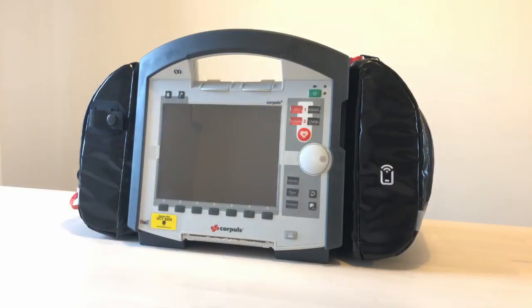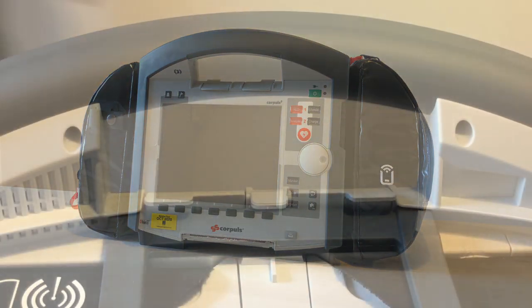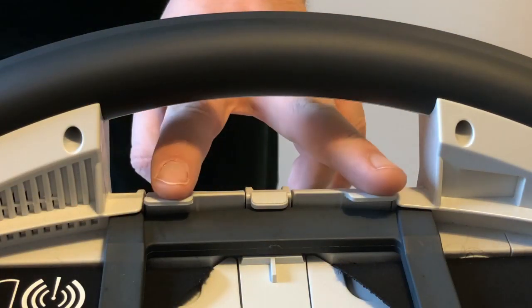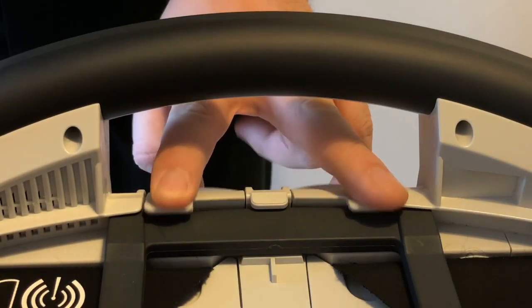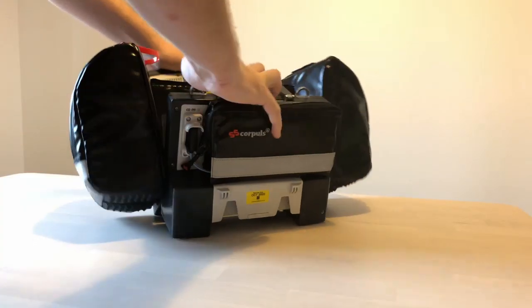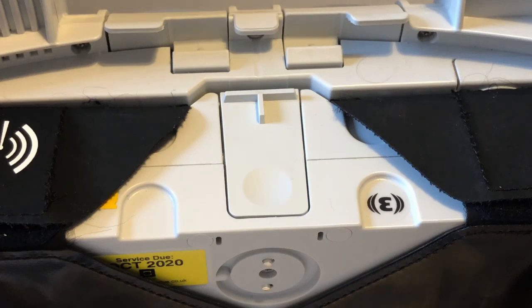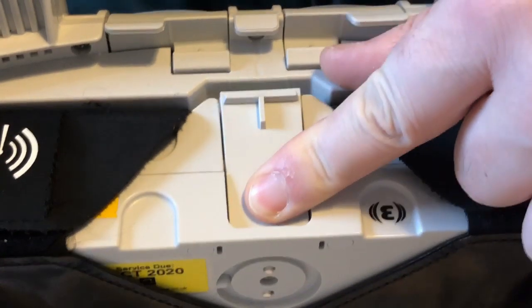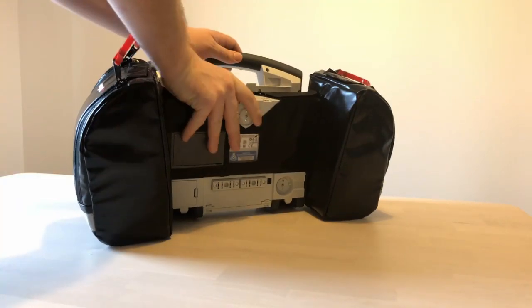The Corpuls3 is a modular device and can be split into three component parts: a control screen, a patient monitoring box, and a defibrillator. The defibrillator is released by pressing on these two tabs underneath the main carry handle, and the defibrillator module can then be removed from the rear of the device. The patient box is released by pressing on this dimpled release mechanism, then the patient box can be removed.